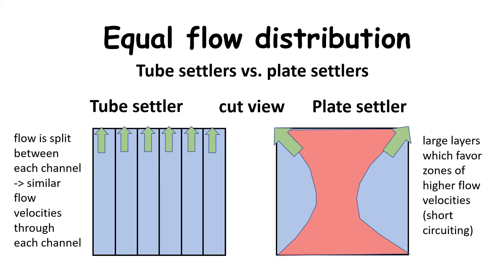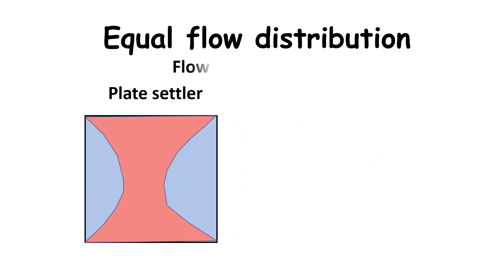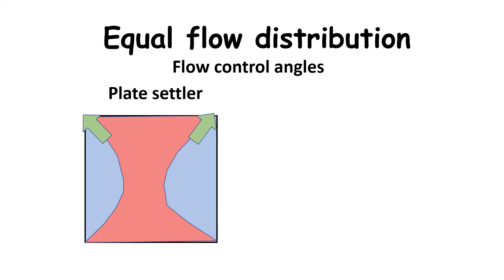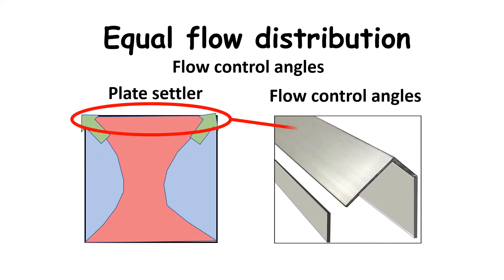If this happens, the settling surface area of plate settlers is not fully utilised so that the clarifier capacity can decrease significantly. Some plate settler manufacturers are aware of this problem and try to overcome the short-circuiting by reducing the channel sizing and adding flow control angles at the top of the plate to limit water flow in certain areas.